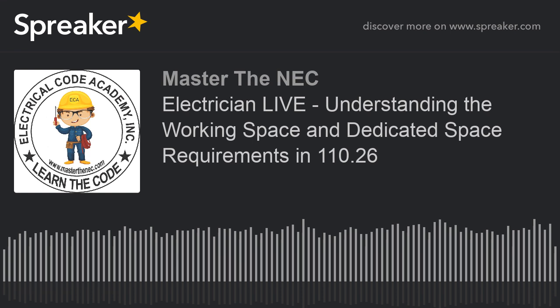So it says on table 110.26A1, which is going to give us these working space requirements. It says unless the requirements in 110.26A1A, A1B, or A1C are met. Okay. So we do have some A, B, and C applications we'll talk about. But other than that, you use the table and you follow the table. And if you have conditions where A1A, A1B, and A1C are applicable, then you get to use these applications. All right. Now, they're not exceptions. They're direct referenced here. Okay.